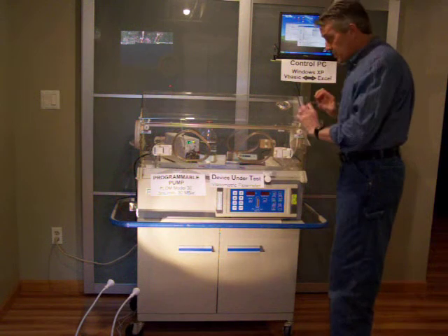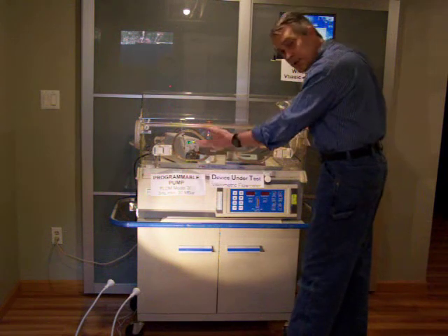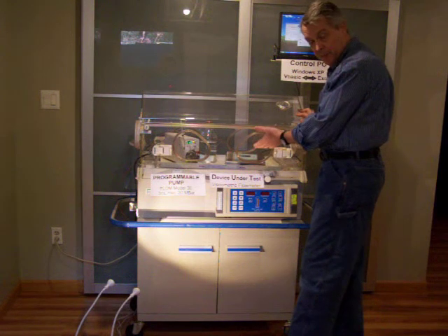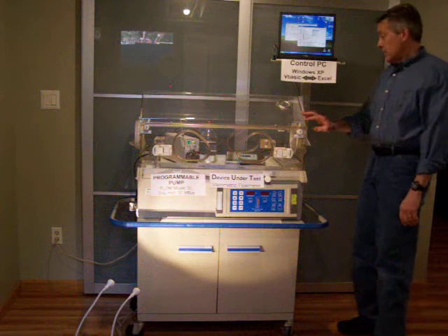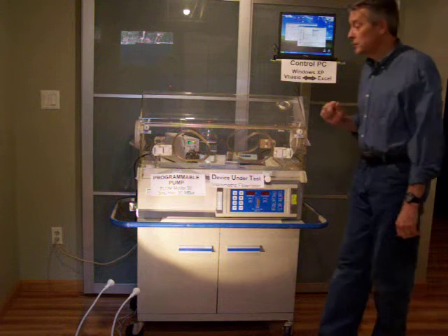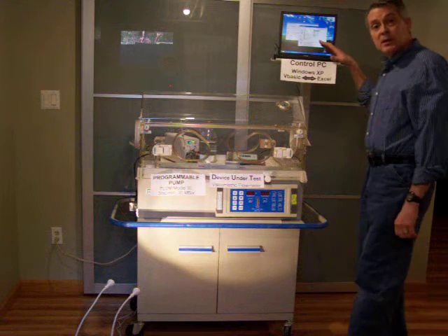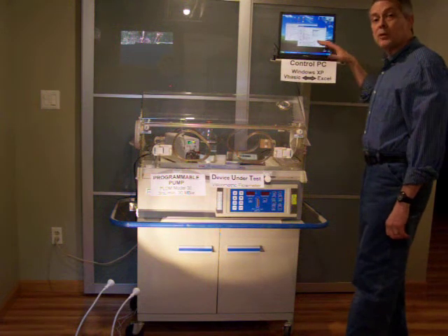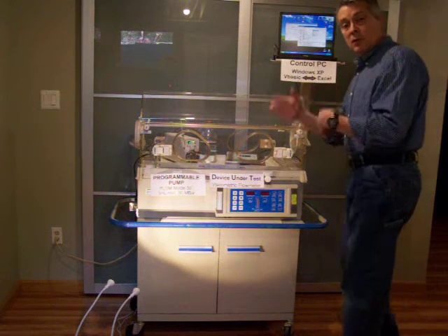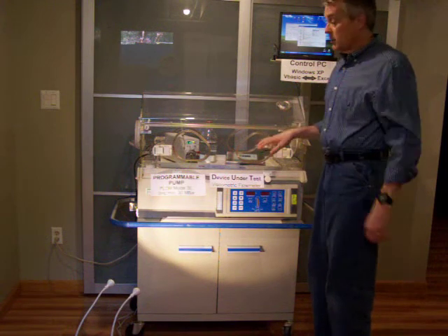The overall system is housed in an infant incubator to control the temperature of the devices under test, in this case a programmable pump and a liquid flow meter, a viscometric flow meter, which is patented by myself. The patent is 7,644,632. The devices are controlled by a PC running a Visual Basic program, which takes script files from Excel and then synchronizes a collection of data and writes the output data from the device under test to Excel.